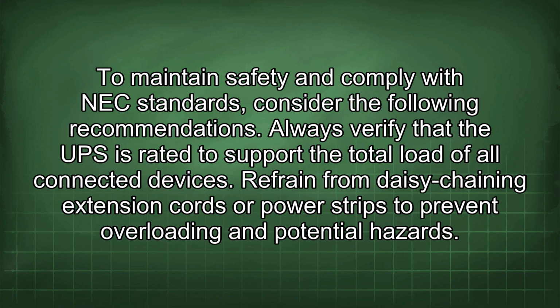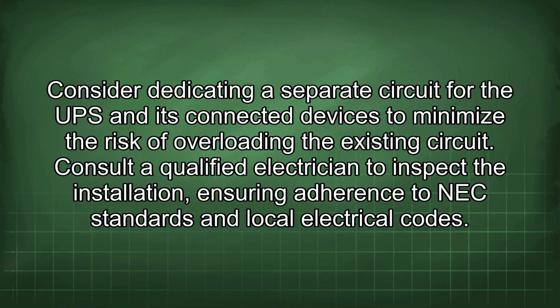To maintain safety and comply with NEC standards, consider the following recommendations. Always verify that the UPS is rated to support the total load of all connected devices. Refrain from daisy-chaining extension cords or power strips to prevent overloading and potential hazards. Consider dedicating a separate circuit for the UPS and its connected devices to minimize the risk of overloading the existing circuit. Consult a qualified electrician to inspect the installation, ensuring adherence to NEC standards and local electrical codes.